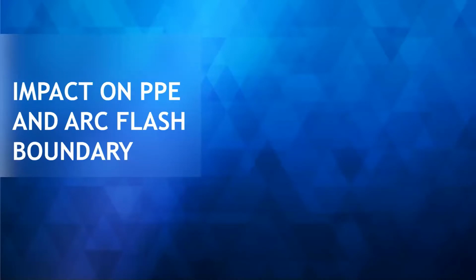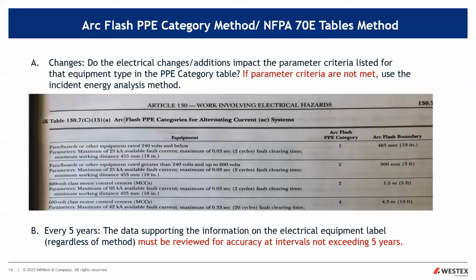So let's look at the impact of changes to your electrical system, or additions, on the PPE and the arc flash boundary. Now, if you're doing the PPE category method, do the electrical changes or additions impact the parameter criteria listed for that equipment type in the PPE category table?